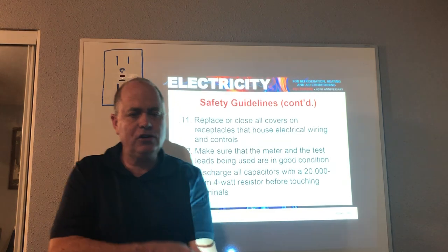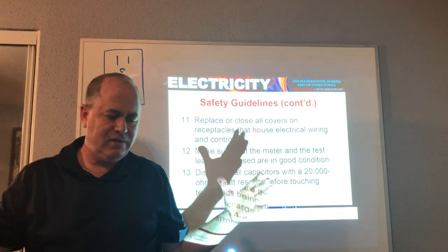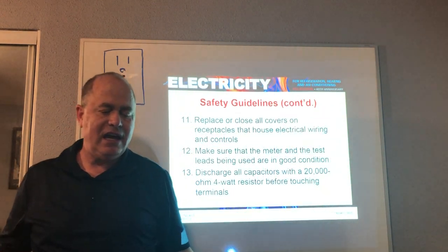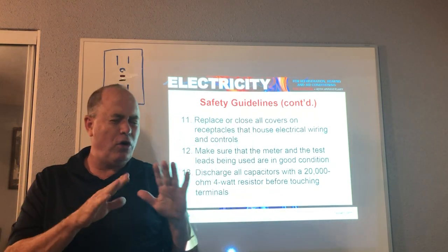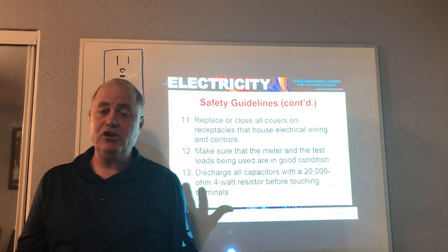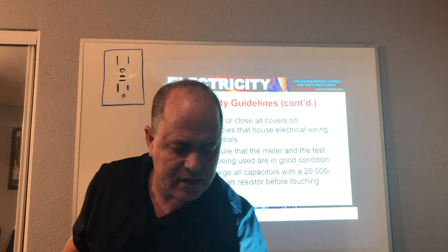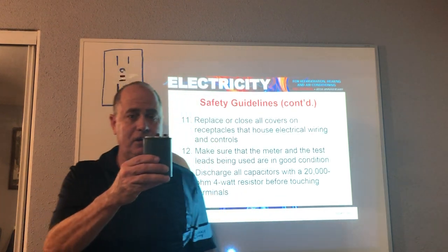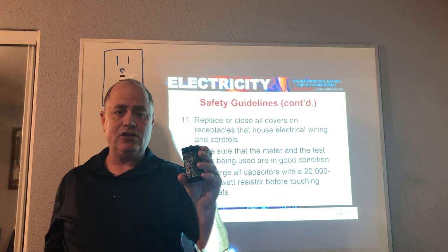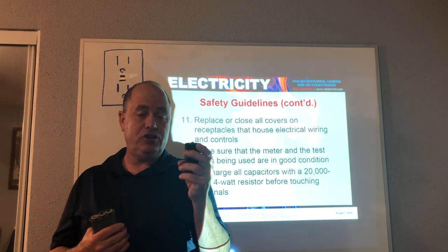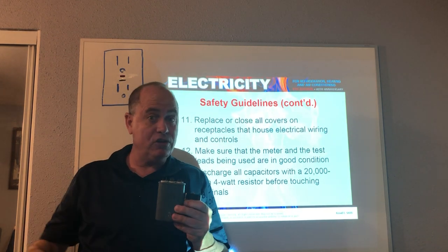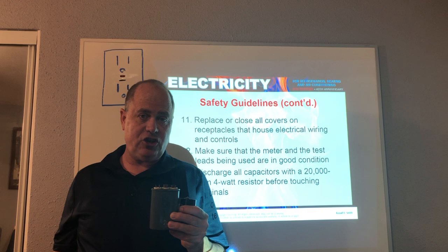Now, capacitors take a charge and give a boost, and they hold that little boost for a while after equipment is shut off. So even if you throw the disconnect, things like a run capacitor or start capacitor can hold a charge for a while. Even though the power's off, if you touch them, you could get shocked.